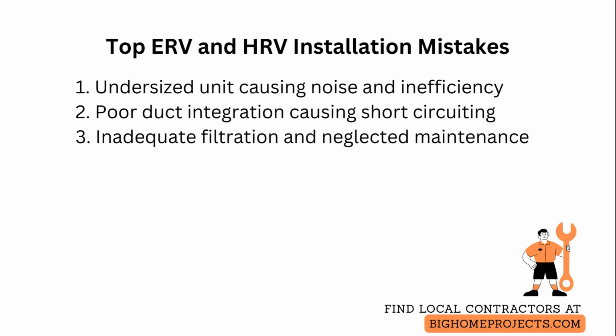Another frequent issue is poor duct integration that causes short-circuiting of intake to exhaust or creates pressure differences. Fix that by connecting to the central return plenum, avoiding long uninsulated runs to outside walls, and balancing flows at commissioning.